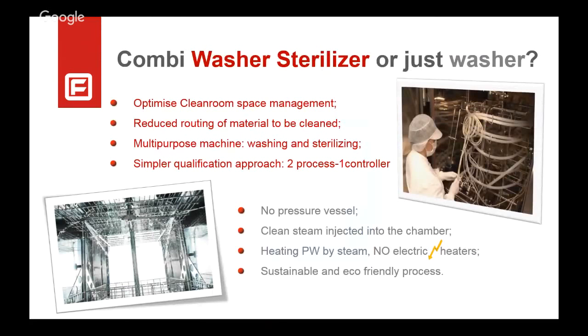So let's go back to the washer sterilizer technology. This is something that we have developed for many years in Fedegari with the Combi machine. So we have both the Combi, with the process of washing and sterilizing with the pressure vessel, or just the washer. Both of them can be used, depending on the initial bioburden of your material, of the kegs. For sure, the Combi solution with washing and sterilizing is very good to optimize the clean room space and to have good space management, also to reduce the routing of material to be cleaned.